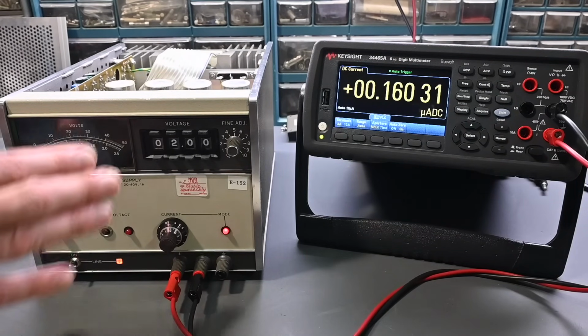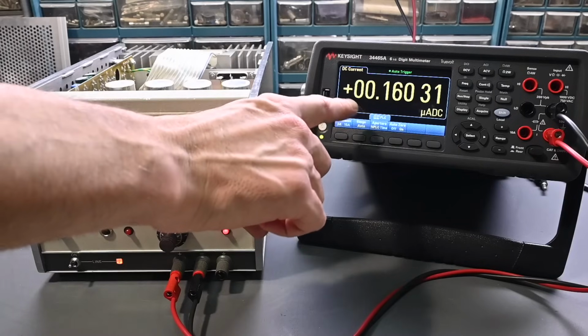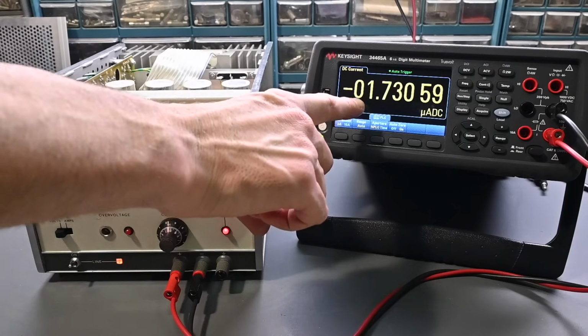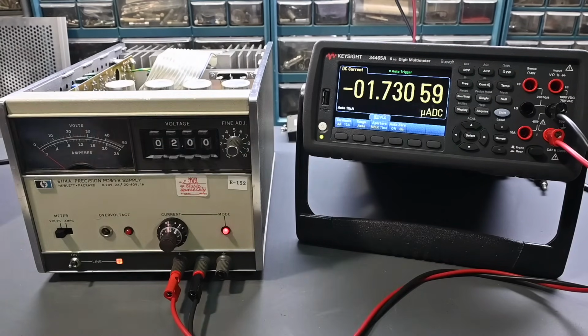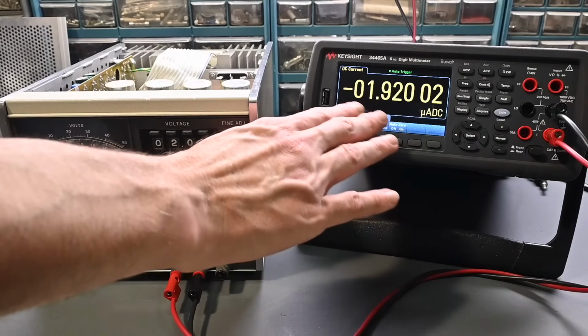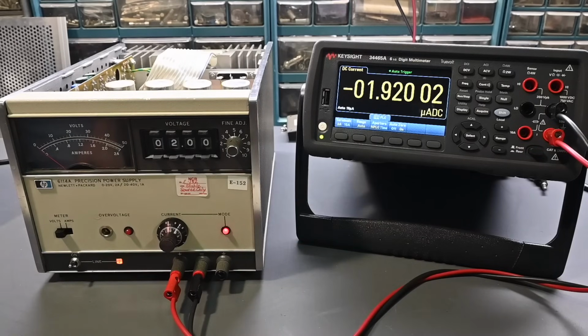Well, check it out. I've made the adjustment already, and look at this. We're well within that spec. That's just 1 microamp, a negative 1 microamp. But that's fantastic. So again, the range would actually be plus minus 100 microamps. So I'm very happy with the result. And the actual adjustment that you make inside the power supply, assembly number 2, it's R12. So yeah, I made that adjustment and it dialed right in. But it was a ways off. It was not near this value when I started.